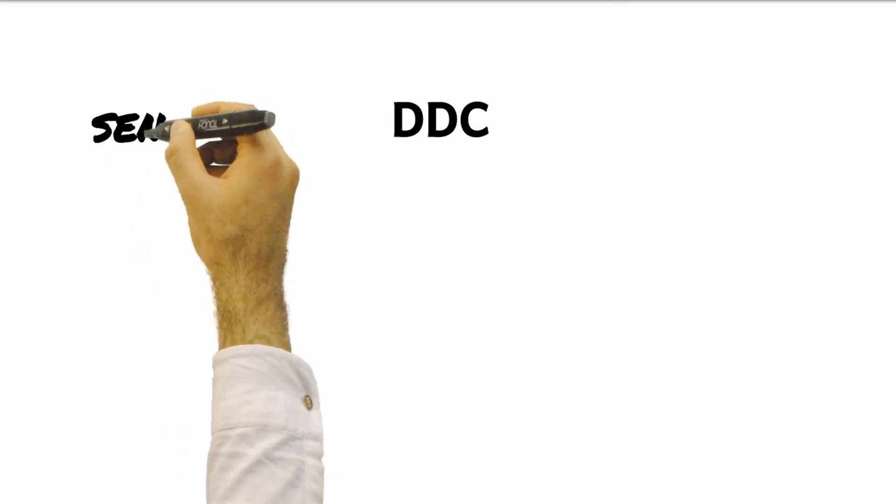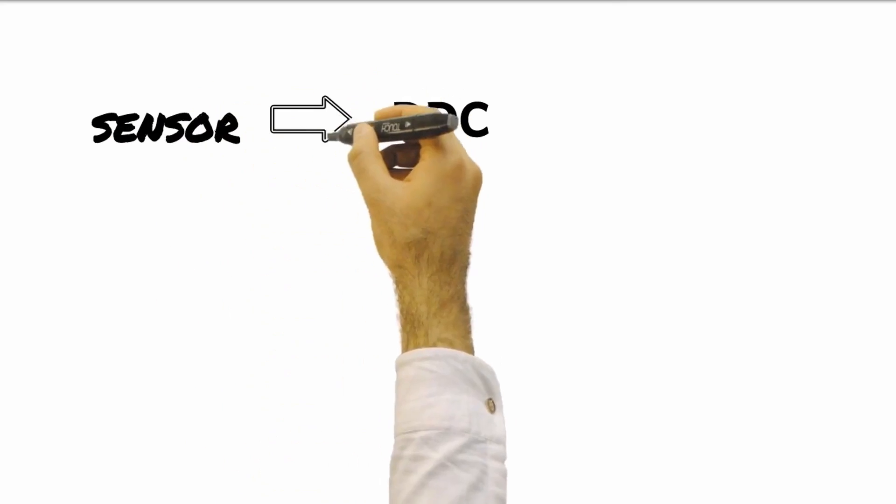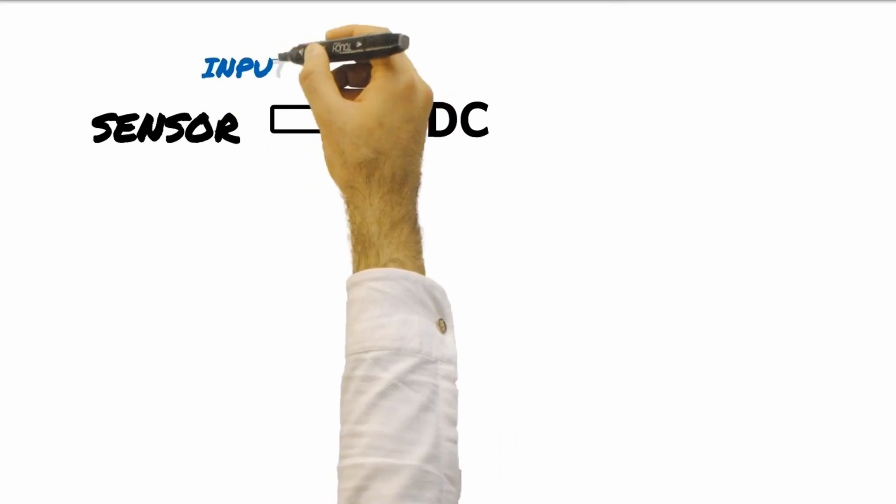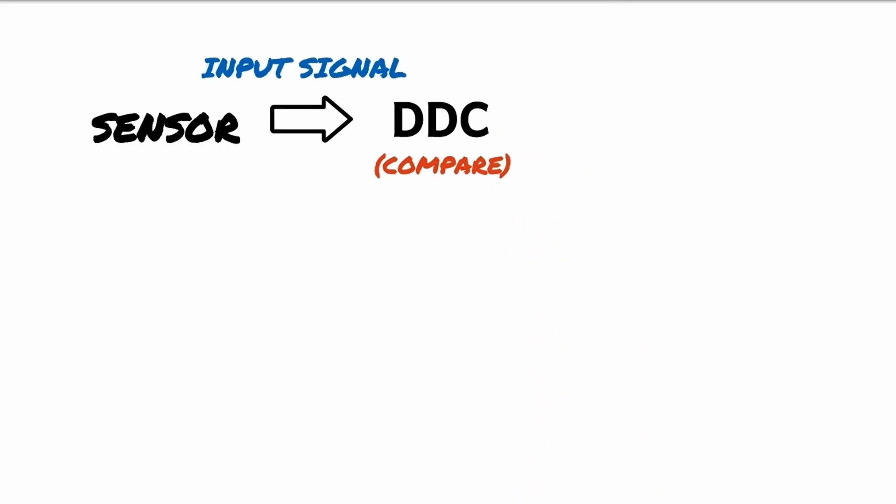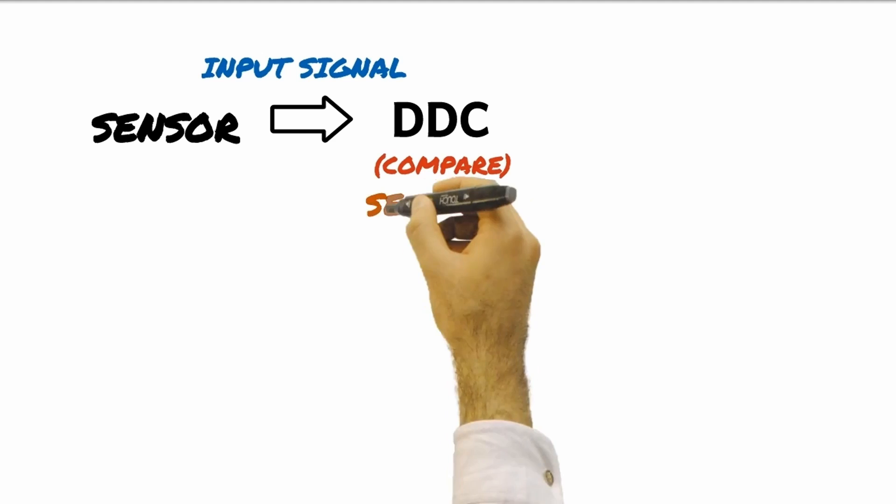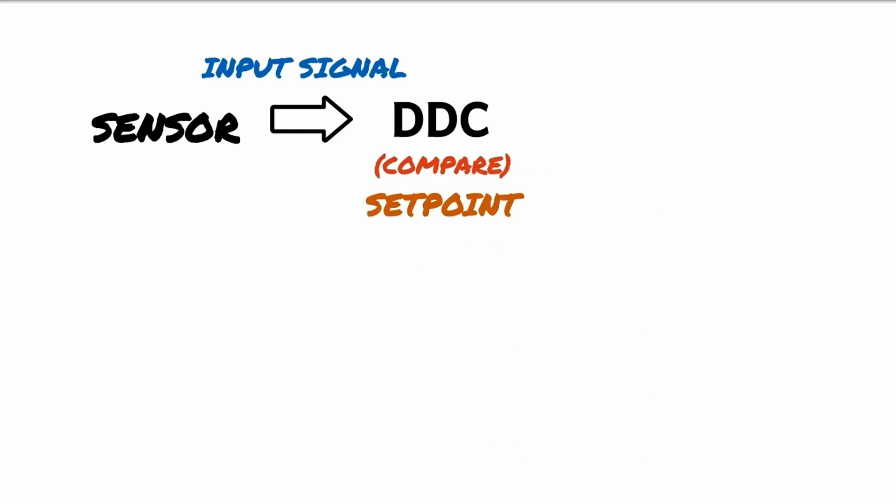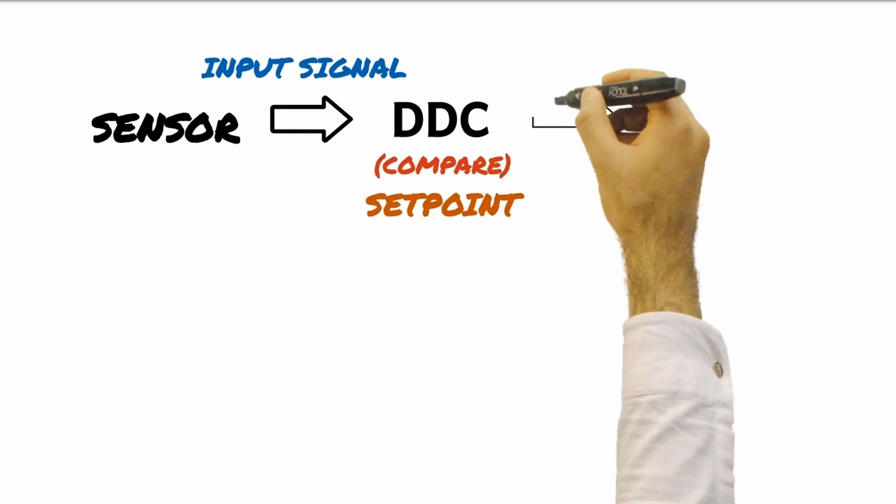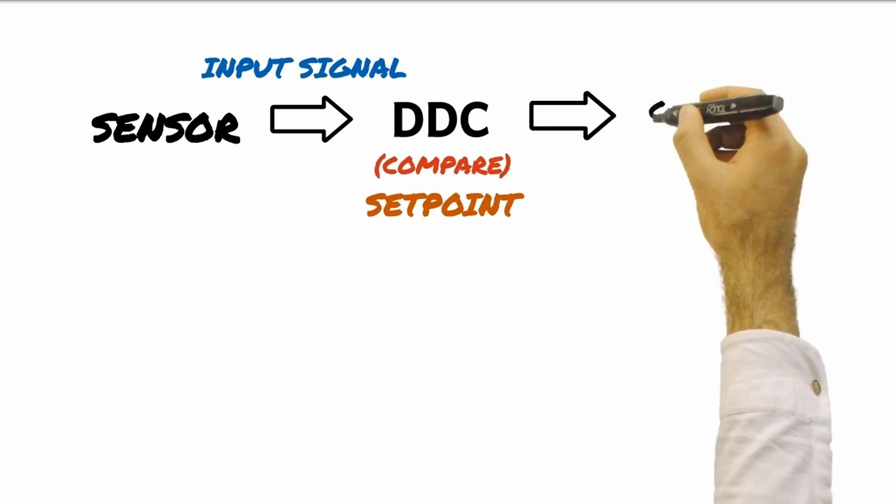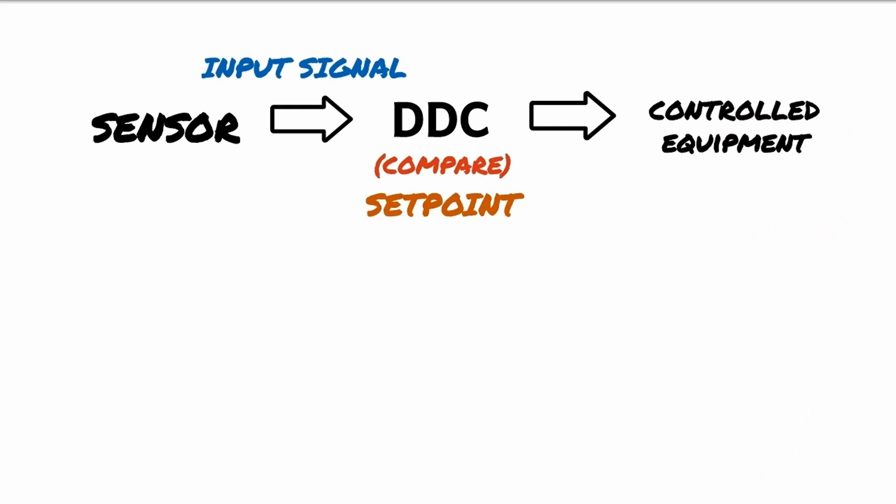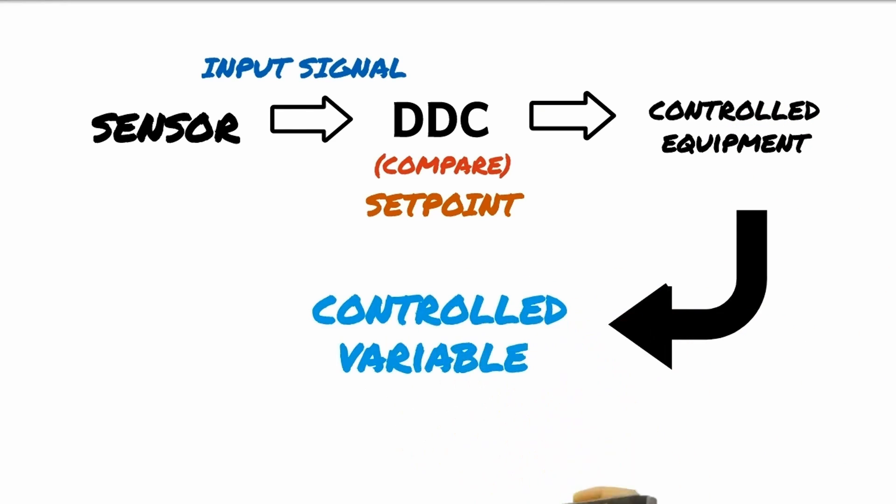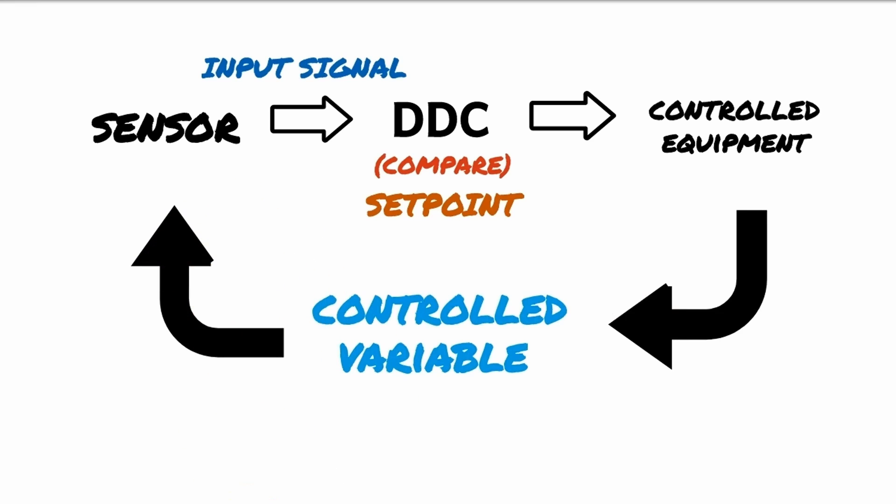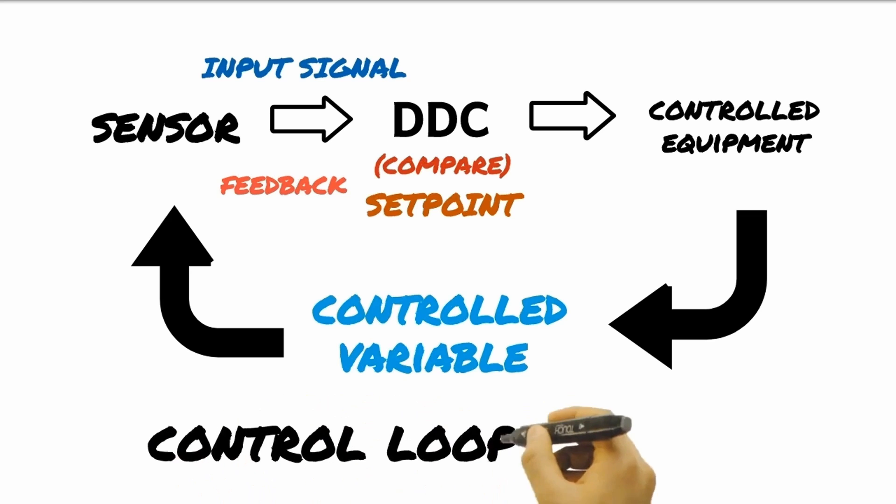When the DDC receives signal from the input devices such as the sensors, the value of the input signal is compared to a certain value that is desired or maintained by the system. This desired or maintained value is called set point. When the input goes out of the set point range, the DDC will then give command to operate certain pieces of equipment to bring back the value of a controlled variable within the set point. The new value is then sent back and measured again by the sensors. This is called feedback and then fed again to the DDC to repeat the process. This whole process is called control loop.